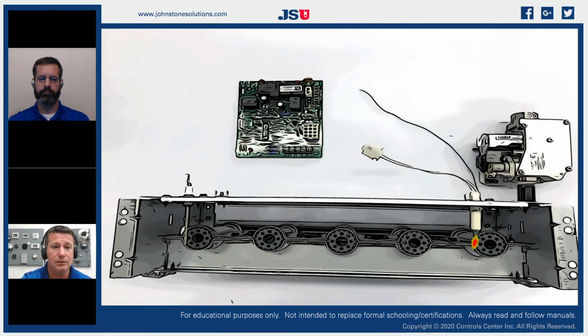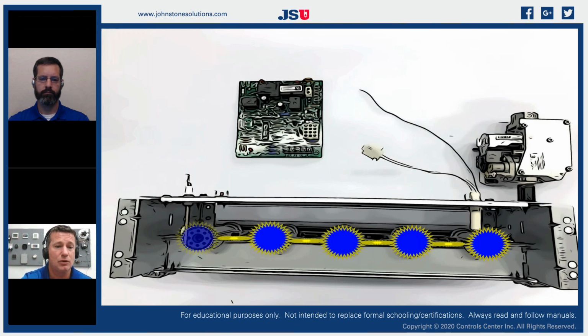We are going to now use a hot surface igniter most of the time. Sometimes we'll use a spark to pilot system, but eventually we're doing the same thing. We're going to allow a combustion point. We're going to add fuel, which is going to allow our flames to pass across our complete burner assembly.